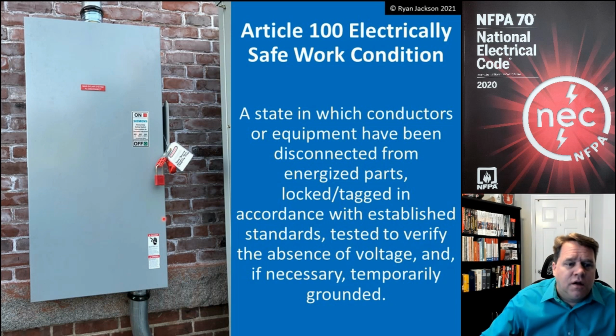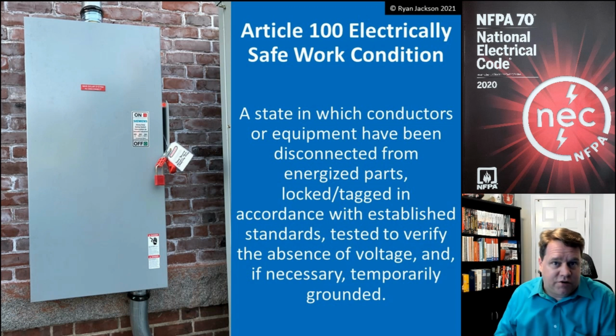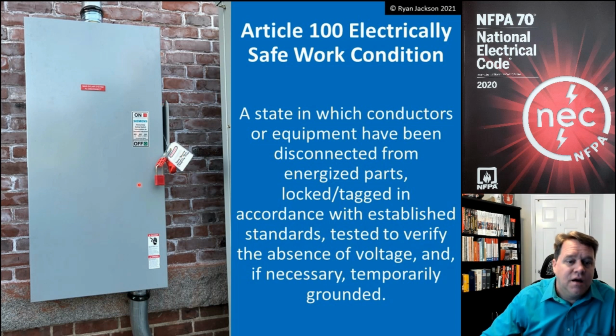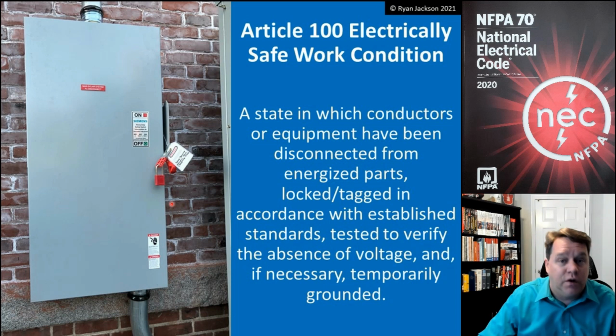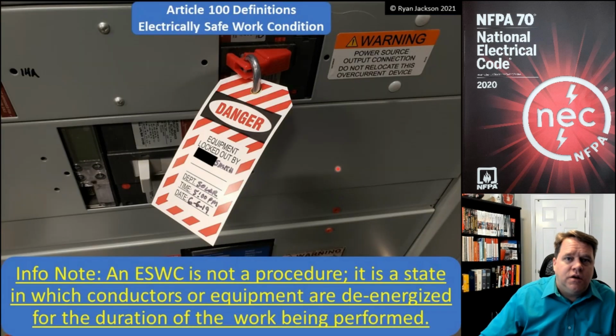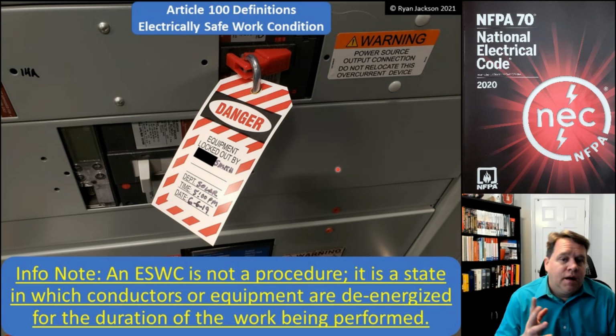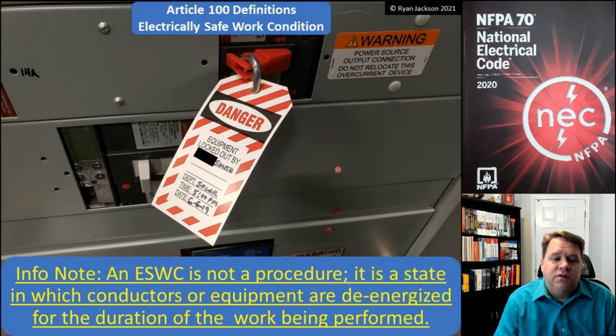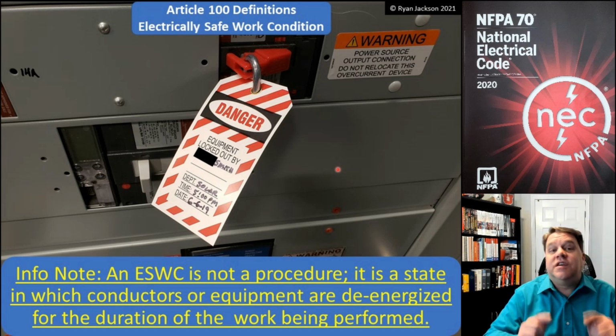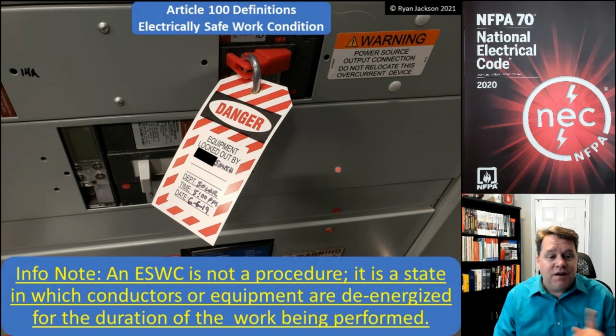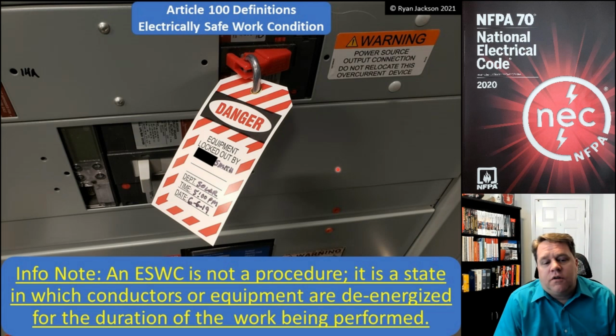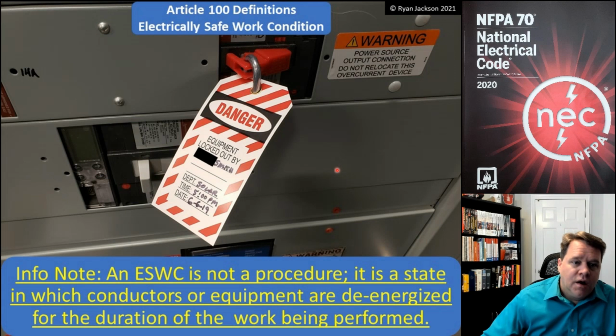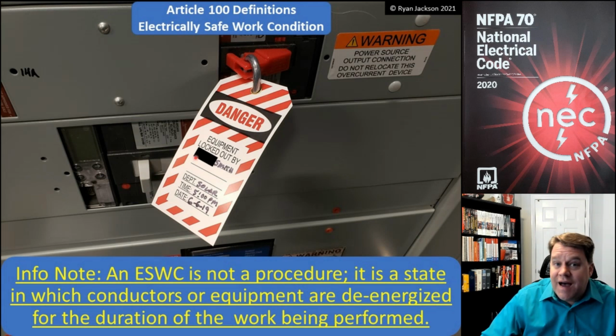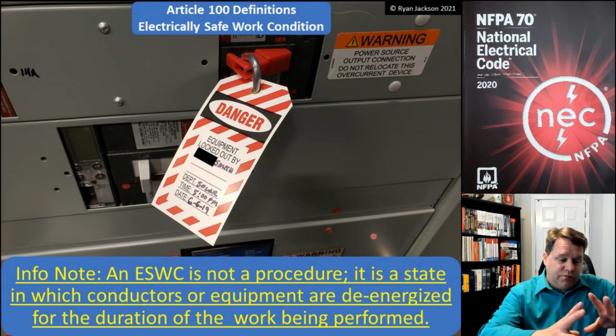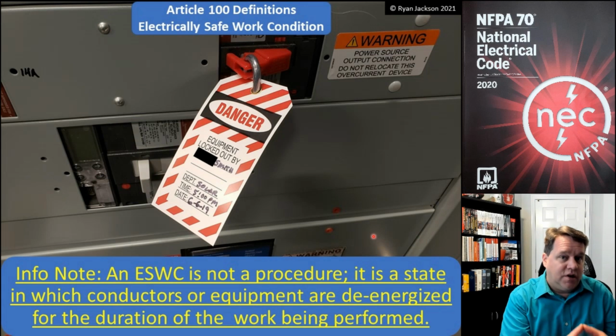Looking at this photograph, this is either in an electrically safe work condition or it's in the process of becoming in an electrically safe work condition, right? We've got the lock, we've got the tag, so we're at least halfway through the process, and perhaps we're all the way through the process. If we read the new informational note that was added in the 2021, it tells us that an electrically safe work condition is not a procedure, it's a state. It's the end result of a procedure in which the conductors or equipment are de-energized for the duration of the work being performed. All right, so this thing is locked out, it's got a tag on it. This is at least halfway through the process of becoming an electrically safe work condition.